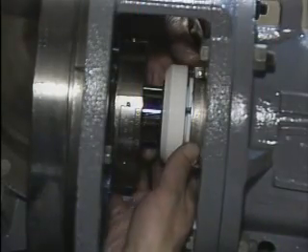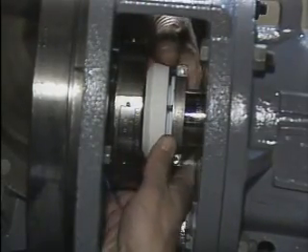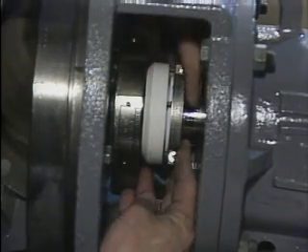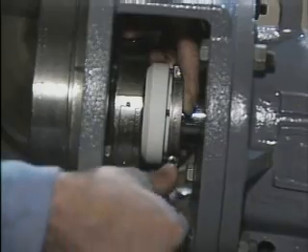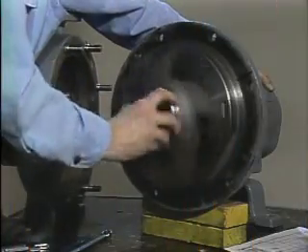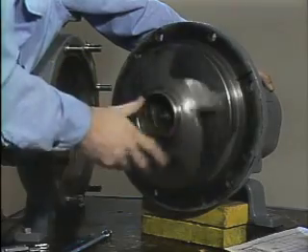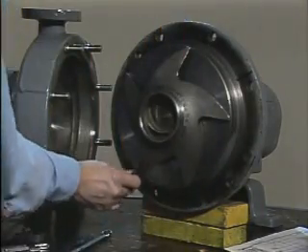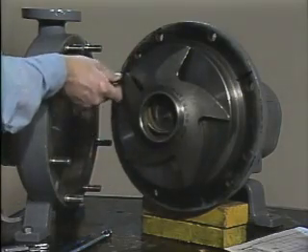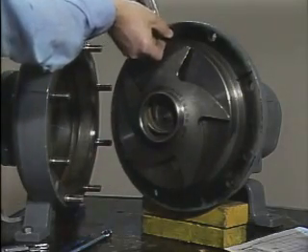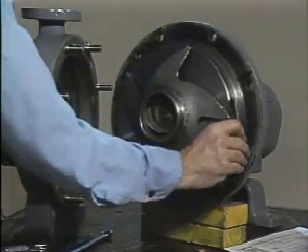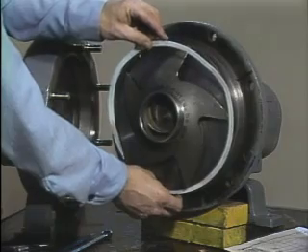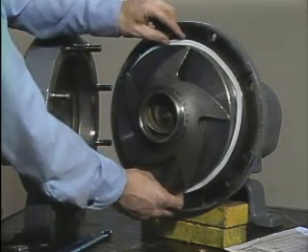Next, the rotating element is put into position so its collar is aligned with the scribe line that was made on the shaft when the location dimension was measured. Then the clamping screws are tightened. After the rotating element is in place, the impeller is installed and tightened. Then impeller clearance is checked and compared with the manufacturer's specifications to be sure that the components have been installed correctly. Once that's done, the seal installation is complete and the pump is ready to be reassembled so it can be returned to service.